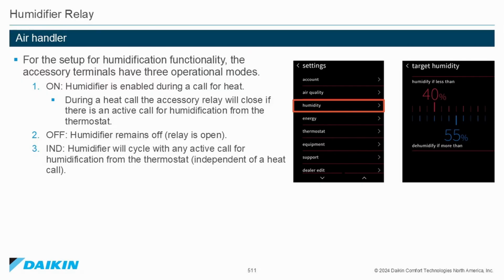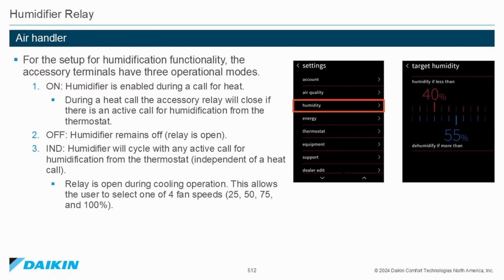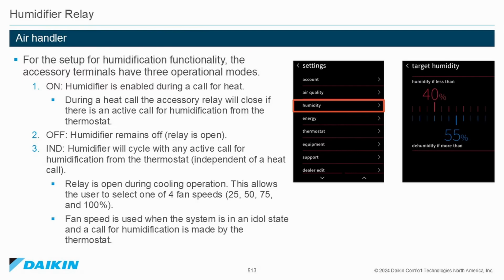3. Independent. The humidifier will cycle with any active call for humidification from the thermostat independent of a heat call. Relay is open during cooling operation. This allows the user to select one of 4 fan speeds: 25, 50, 75, and 100%. Fan speed is used when the system is in an idle state and a call for humidification is made by the thermostat.